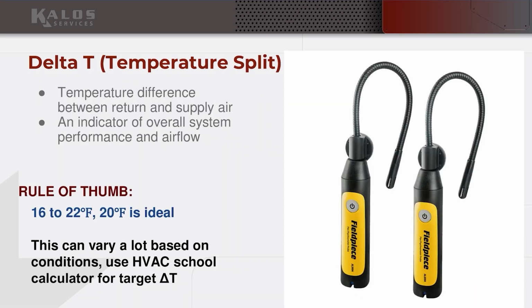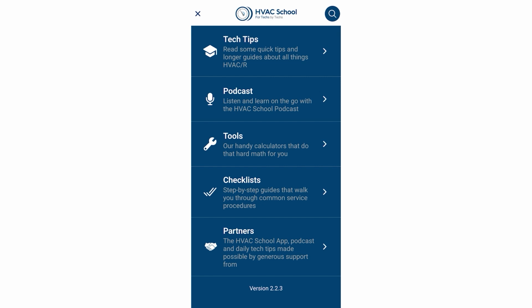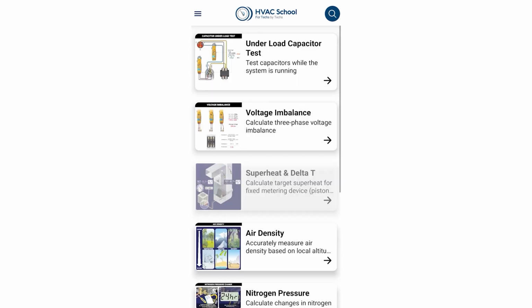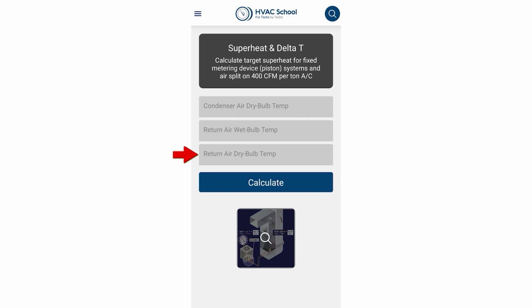So your target temperature split is going to vary a lot. 20 is ideal. I think I put 16 to 22 on there. You can calculate it. There's a calculator in the HVAC School app where you give it your return temperature dry bulb, your return temperature wet bulb, and your outdoor ambient. You plug in those values and it'll spit out a target delta T and also a target superheat for charging a piston system, because they're related.